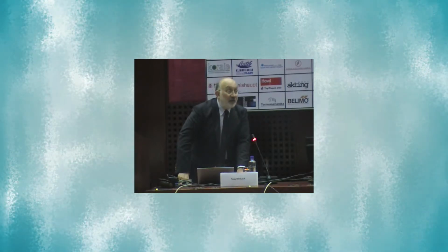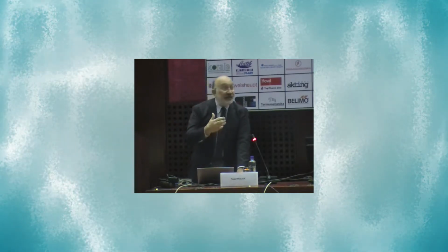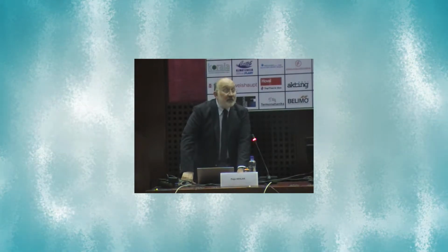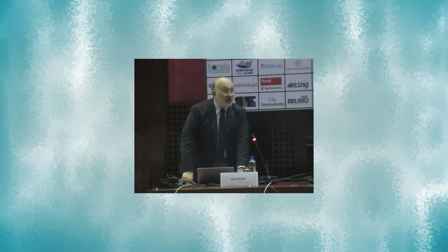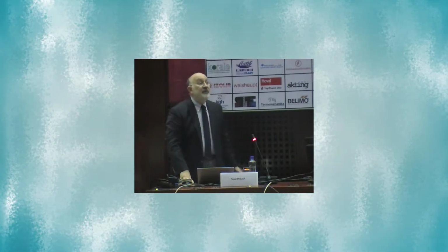We know that well. In condensation, you wouldn't have a very strong effect of heat flux, but you will have a strong effect of mass flux. But this is evaporation. So these are the data. Look at this. Even now, you see that this is between 4 and 5,000, but over here, we used to have something between 2 and 3. So heat transfer is up. We already see that. Now, how about pressure drop?